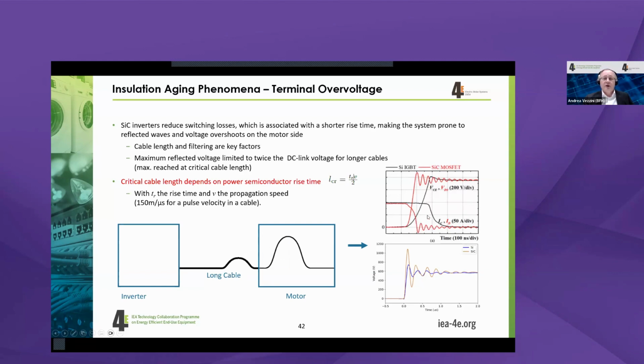So all the technology advancements which have been done on the insulation properties for IGBT-based inverters have now to be re-questioned and seen if this is also possible for the switching speed of silicon carbide. The switching speed will lead to over voltages, and this over voltage is heavily dependent on cable lengths and filtering at the output of the inverter. So we could have filters directly at the output of the inverter and therefore decrease the impact, or without a filter, the cable length is basically the most important factor.